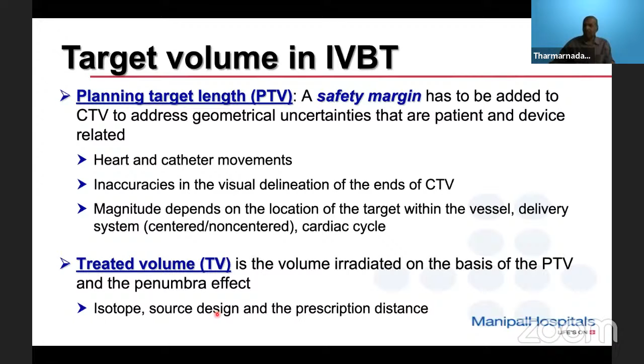This safety margin will address heart and catheter movements, and also the inaccuracies in the visual delineation of the ends of the CTV. The magnitude of the safety margin will depend on the location of the target within the vessel, the delivery system, whether we are using centered or non-centered, and also the cardiac cycle. And the treated volume is the volume irradiated on the basis of the PTV and also the penumbra effect. So this treated volume will depend on the isotope, the source design, and the prescription distance.